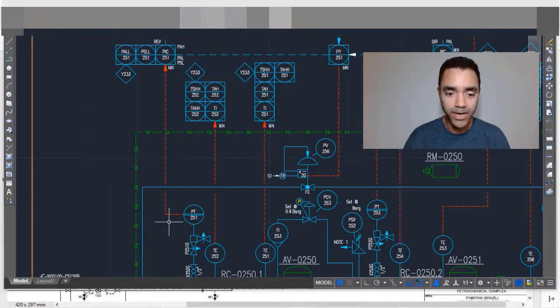So if the pressure decreases and I need to return my pressure to the desired condition, what happens is that the signal that I will send to this control valve is for opening. I am reducing the pressure at the suction and I will increase the signal so this control valve opens. So I have reverse conditions for my process, and because of that it is reverse.